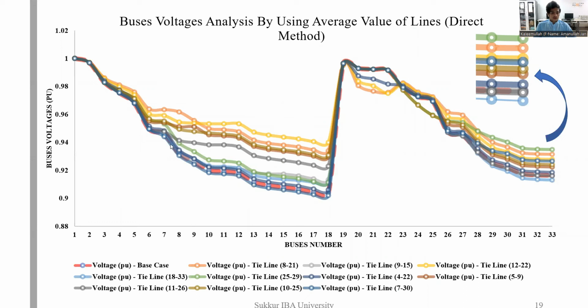So on the x-axis, we have the bus numbers for the IEEE 33 bus system, and on the y-axis we have the bus voltages in per unit. The dotted line shows our voltages in per unit for the base case, while the others show the voltages in per unit for the tie lines. So here we can clearly see that the voltage profile is improved by using different tie lines one by one in the system. So by reconfiguration, we enhance the voltage profile, which is shown clearly in the following graph.